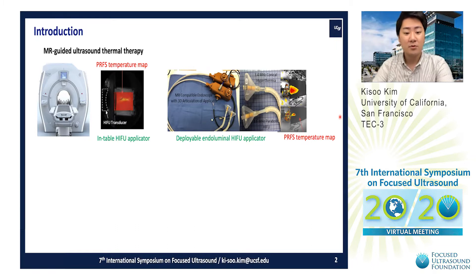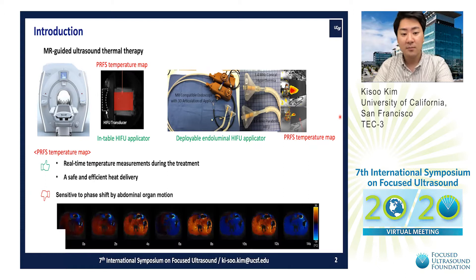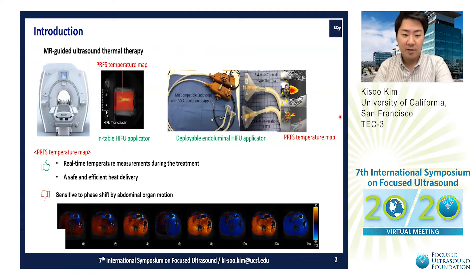It is very important for all researchers studying MR-guided ultrasound thermotherapy that the PRFS method allows for real-time temperature measurements and provides safe and efficient heat delivery. However, it has a fundamental limitation: it is sensitive to phase shift from abdominal organ motion. Temperature errors have a major influence from respiration.